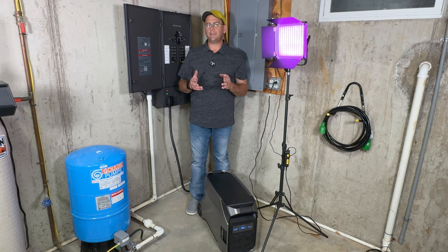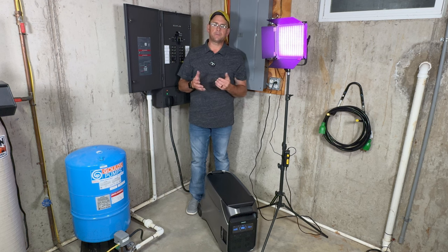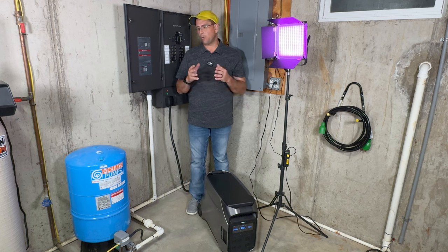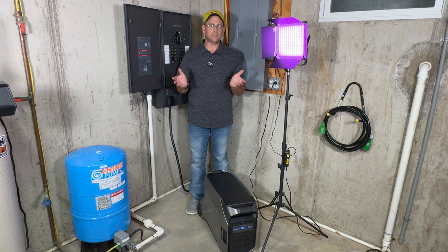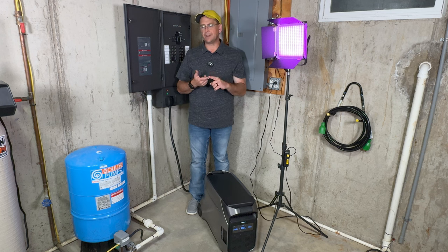So you're usually at 25 seconds to as much as 45 seconds, depending on whether or not that generator starts. If you've seen any of my other videos, a lot of the reasons why I'm making the video is because it didn't start. People didn't even know that they were having issues. So with this being in the house, I've noticed that my portable generators, I've had very few problems with them because they're out of the weather. When things sit outside in the weather, mice get into it, the weather gets into it, things just go wrong, things get forgotten, like batteries going dead was probably one of the biggest things.